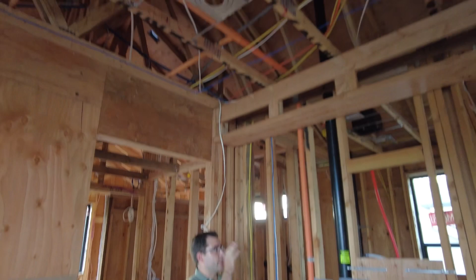It's built to the commercial building code, which requires a sprinkler system if units are separated by floors instead of by walls. If you have tall, skinny units that only share walls, you don't need a sprinkler system because you can get your fireproofing between units in the wall insulation. But as soon as you share floors and ceilings between units, you can't practically get that fire separation, so you have to add sprinklers to get the fire rating, which is why we have a fire riser room.